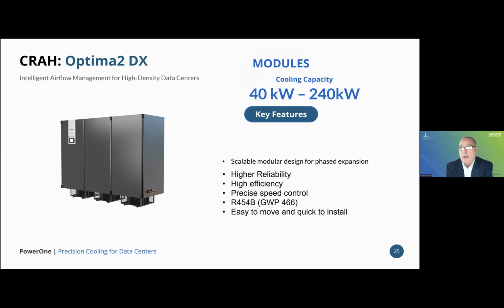Our DX unit. This product has been around for 12 to 15 years. Again, it's based off of the unit with the modules. However, these are in 40 kW blocks, and you can get up to 240 kW. It comes with a heat rejection condenser. It can be either out on the roof or outside the building itself. Highly efficient, and it already comes with the R454B, global warming potential of 466. Again, this will fit right through standard doors, standard width and heights of those doors. So it's easy to move and quick to install.